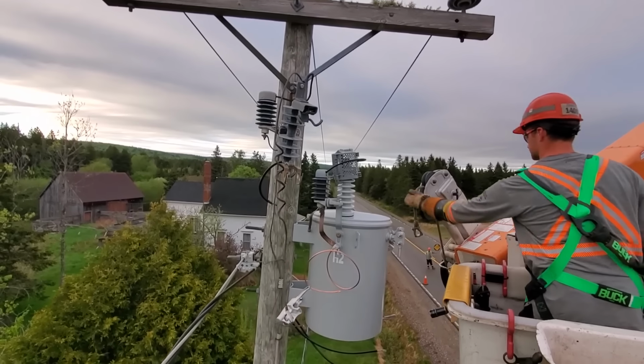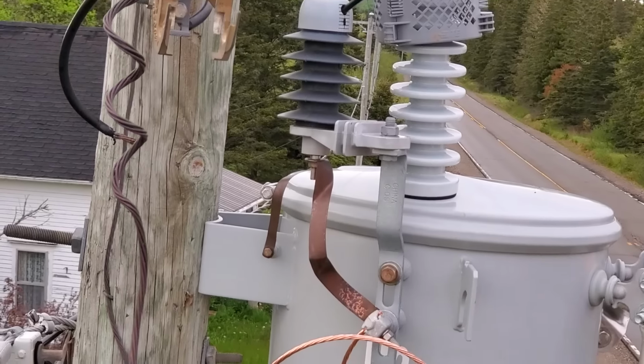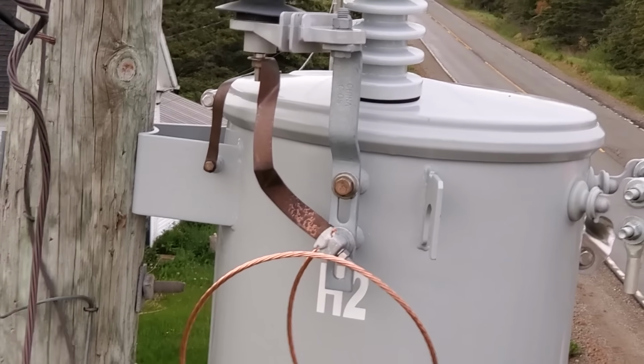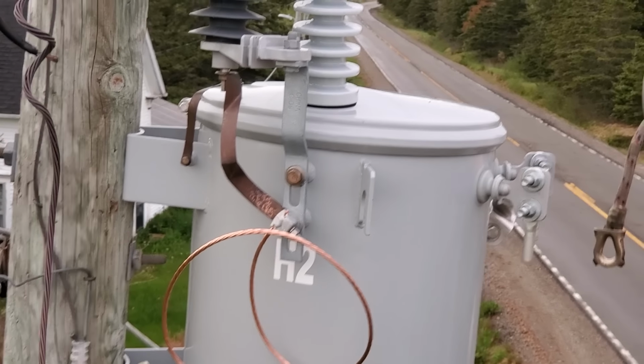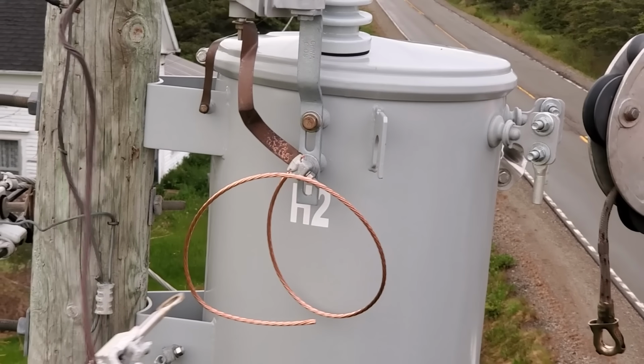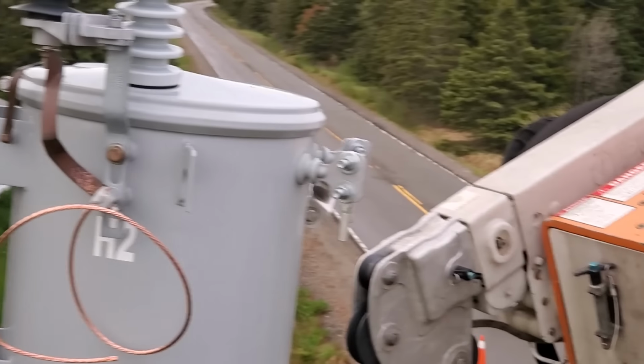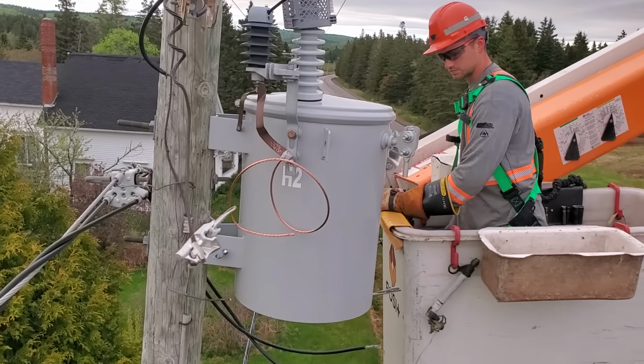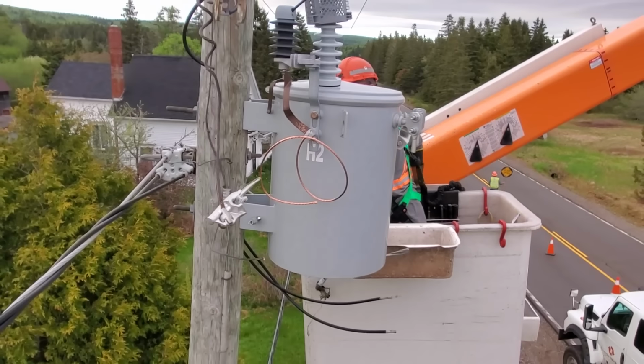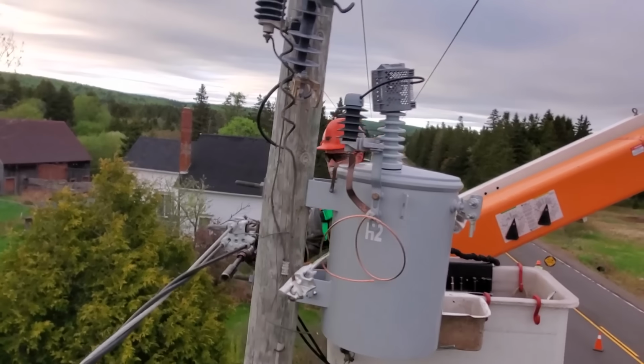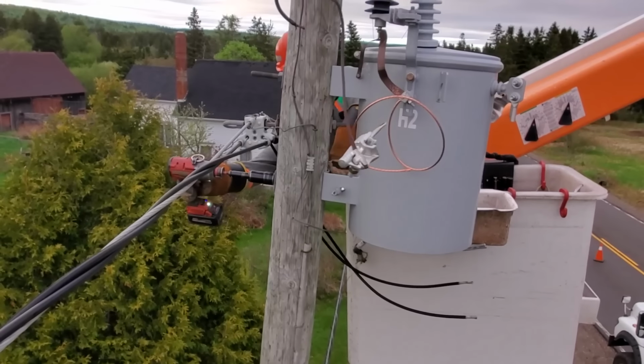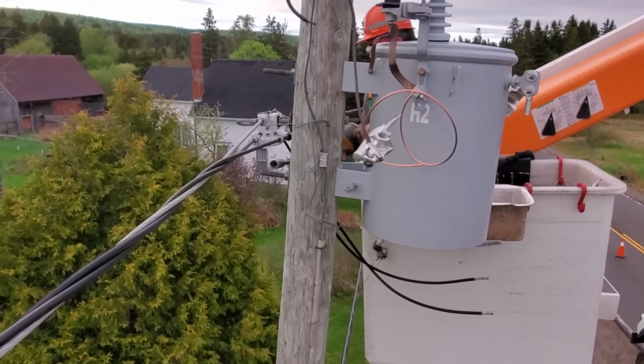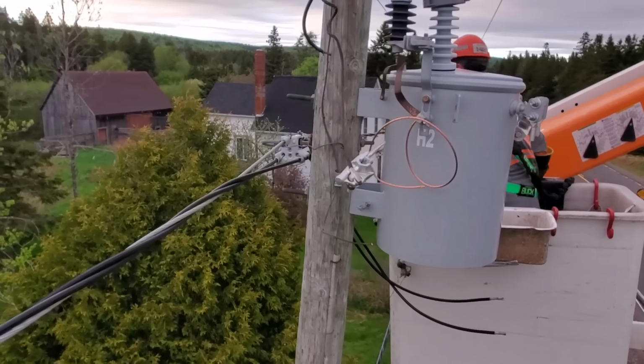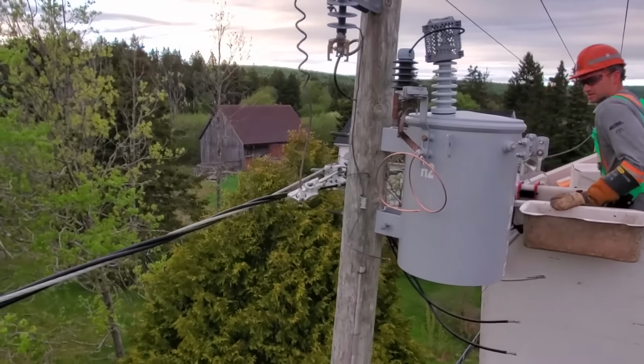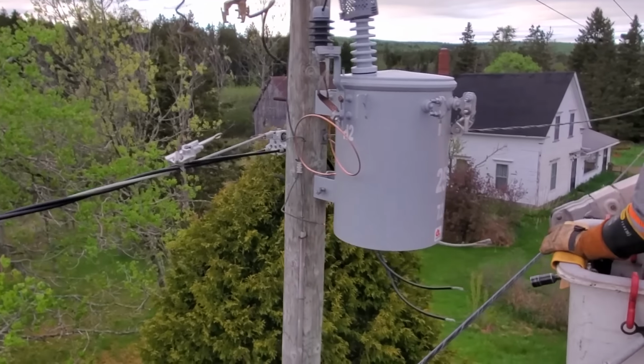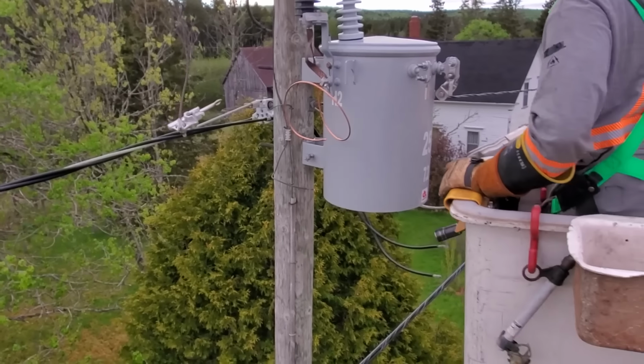So you can see the new lightning arrestor, same style. It's got a bond strap on the bottom side of the lightning arrestor, right onto the H2, which is basically the ground side of that primary winding. It's got a new copper lead on the H2, which will be bonded to the neutral. He's just getting his jib out of the way there now. Next, he's just going to be tightening up that bottom bolt. It doesn't really matter what order we do the rest of this job, other than those secondary leads must be hooked up last.